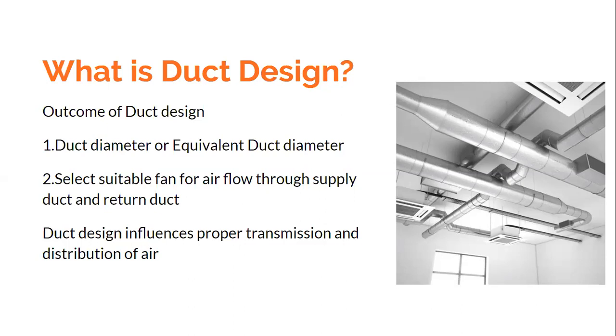If there is a false ceiling, unfortunately you cannot see this very easily. So what duct design means is that you need to know what should be the diameter of the duct to be used, or if it is a rectangular or square duct, you need to know its equivalent diameter. Then you need to select a suitable fan, because if you want air to move through the duct at a particular velocity and flow rate, you need to choose an appropriate capacity fan — that is also included in the duct design.